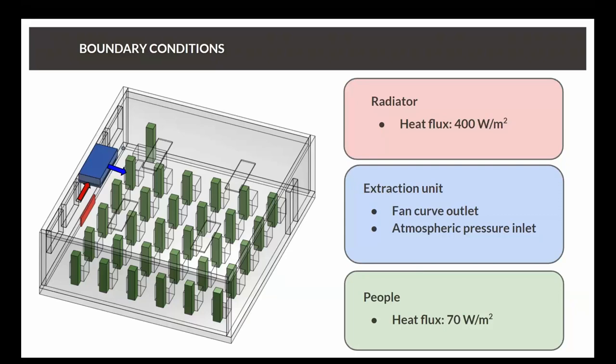And finally, once we have the mesh, the only thing we need to worry about is to define our boundary conditions. So apart from all the walls that can be automatically assigned as a standard adiabatic wall, we need to define both the radiator and the people in red and green in the picture as heat sources, as a heat flux of 400 watts per meter squared and 70 respectively. And then for the extraction unit, we have both conditions like a fan curve outlet from the extraction unit point of view, putting air into the room. And this fan curve means we will be able to input a curve of pressure versus flow rate. So depending on the conditions, you will be putting more or less air into the room. And then just an atmospheric pressure inlet back to the extraction unit in the red flag on the side of the unit.